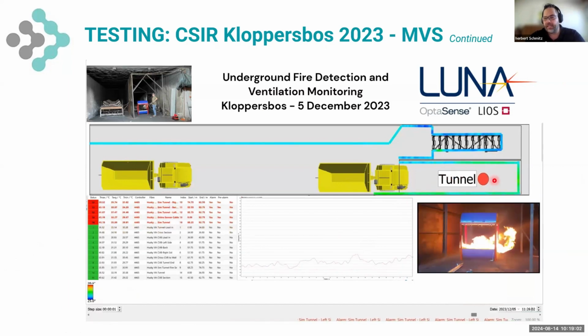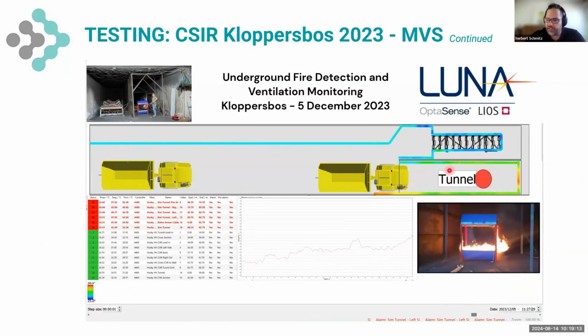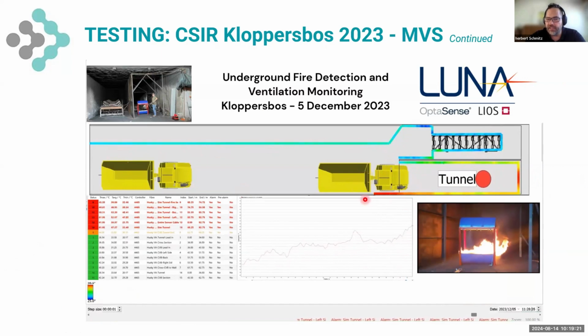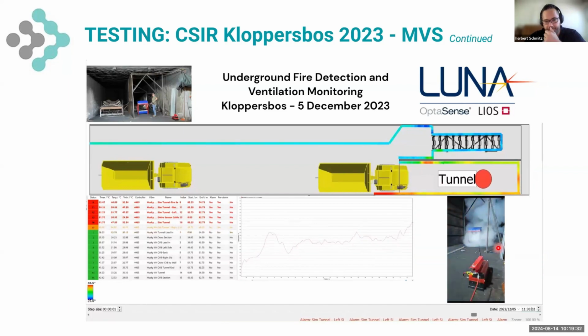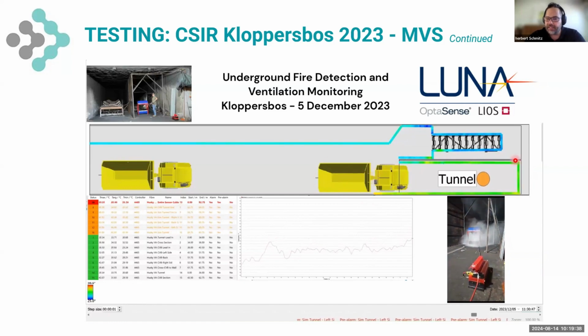Immediately, obviously, alarms on rate of rise. We can see the temperature profile along the entire fiber optic cable and the air movement. We can see in which direction the hot gases and the smoke are moving. We can identify exactly where that fire is. We can see the actual temperatures along the fiber optic cable. We know exactly which zones or sections within that mine. And with the extinguishing system activated, let's say within the machine, we can see how dramatically that section within the mine is cooling off.